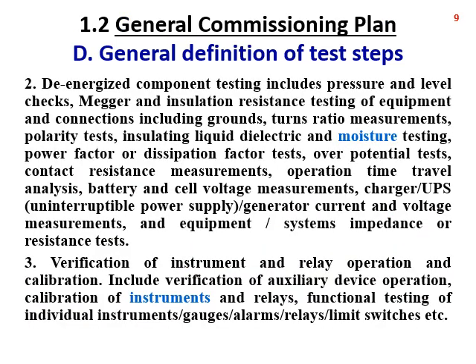General commissioning plan. General definition of test steps. Number 2. De-energized component testing includes pressure and level checks, megger and insulation resistance testing of equipment and connections including grounds, turns ratio measurements, polarity tests, insulation liquid dielectric and moisture testing, power factor or dissipation factor tests, over potential tests, contact resistance measurements, operation time travel analysis, battery and cell voltage measurements, charger or UPS uninterrupted power supply or generator current and voltage measurements, and equipment or system impedance or resistance tests.